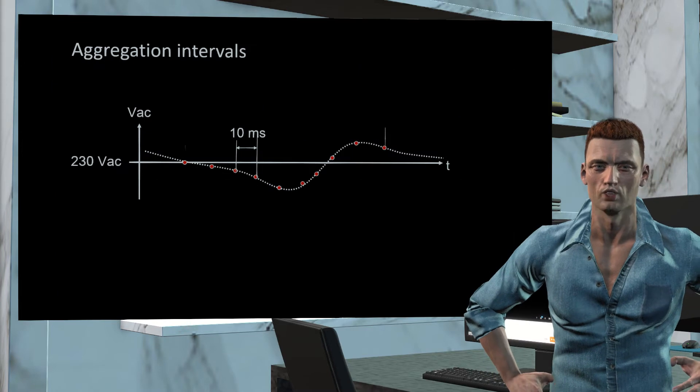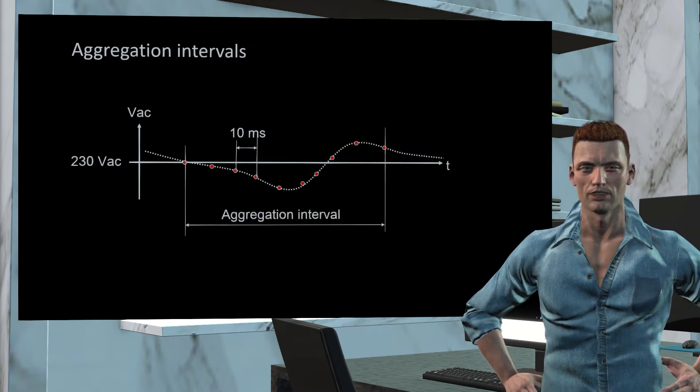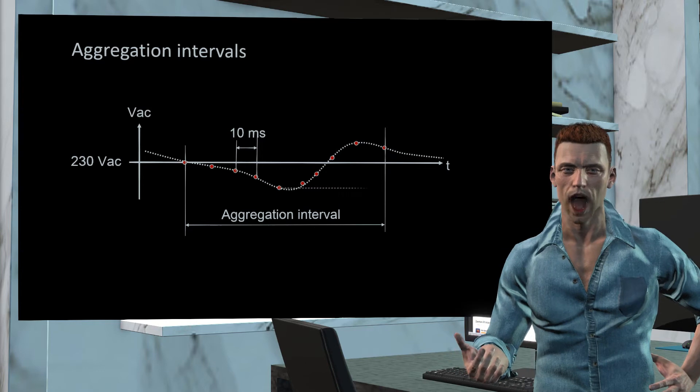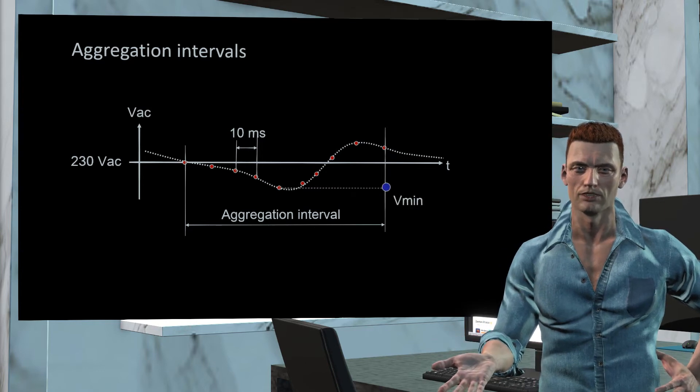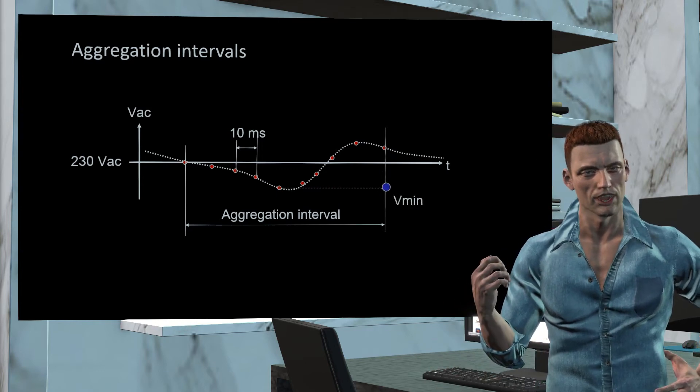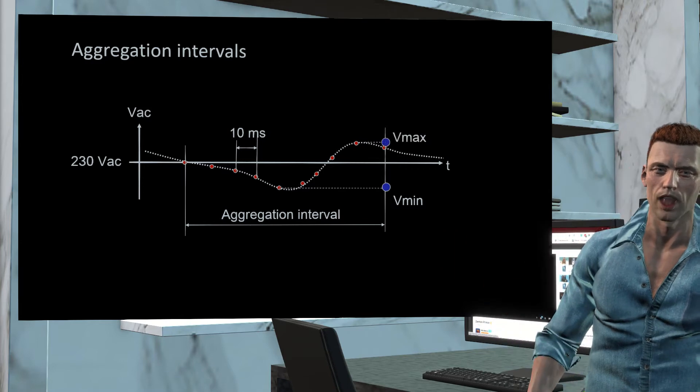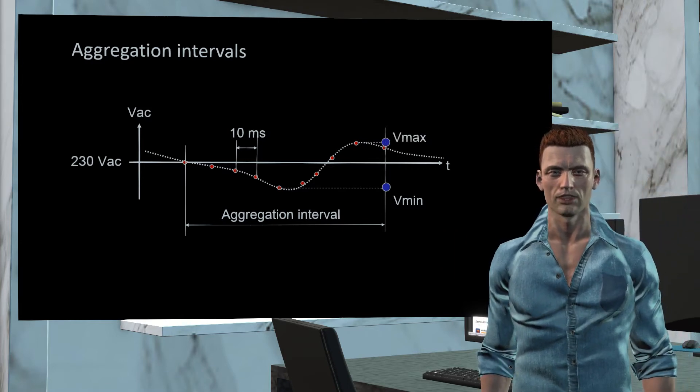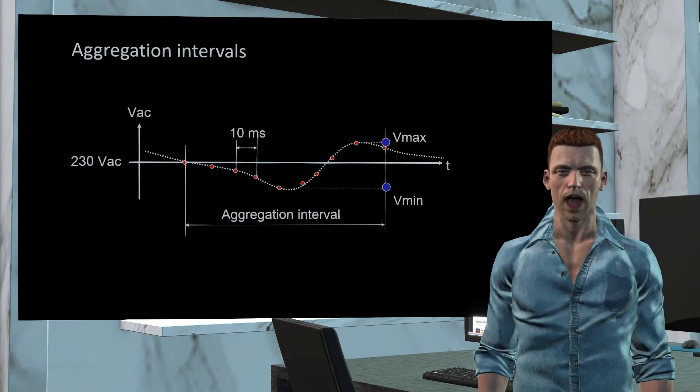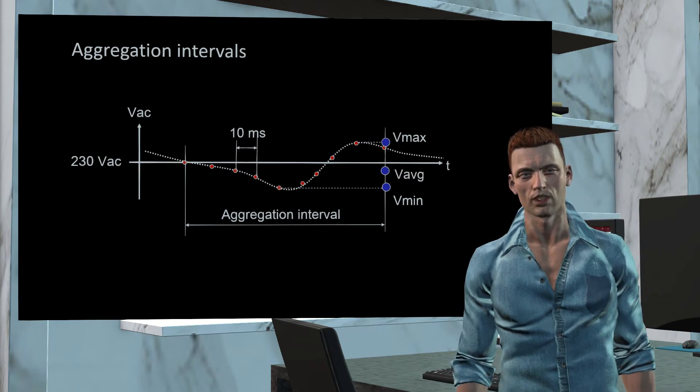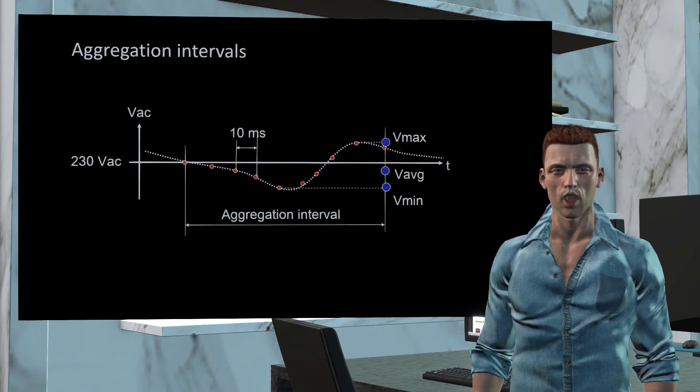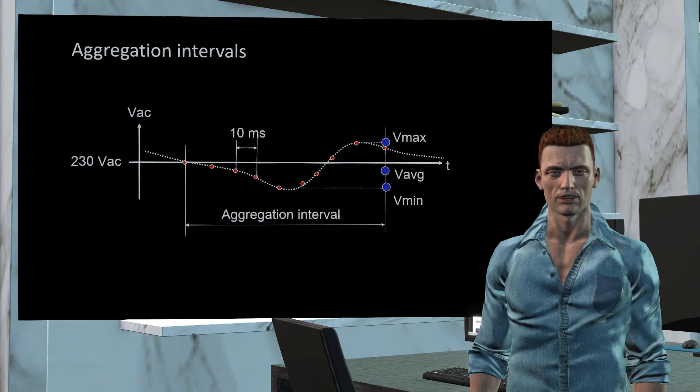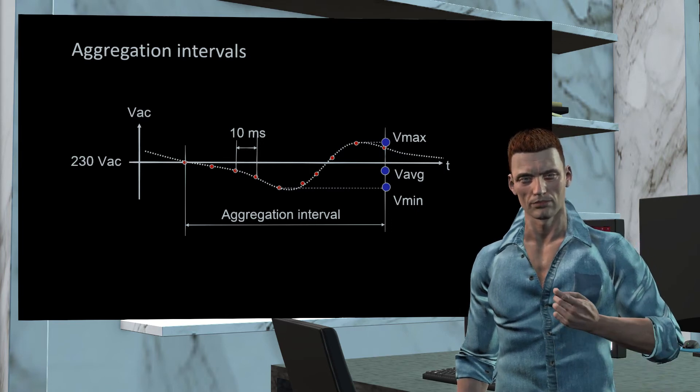However, this does not mean that later with the software, in a trend graph we could see RMS values every half-cycle, or even every 10 cycles. The standard IEC 61000-4-30 also introduces the concept of aggregation intervals. Basically, this standard defines three time intervals, one of three seconds, another one of 10 minutes and the last one of two hours.